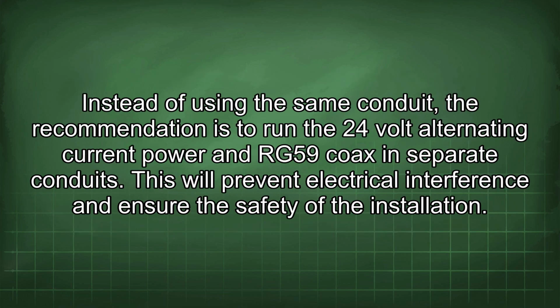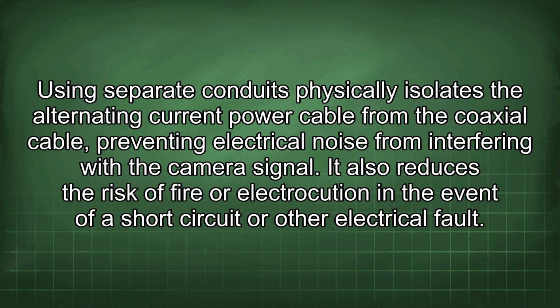Instead of using the same conduit, the recommendation is to run the 24-volt alternating current power and RG59 coax in separate conduits. This will prevent electrical interference and ensure the safety of the installation. Using separate conduits physically isolates the alternating current power cable from the coaxial cable, preventing electrical noise from interfering with the camera signal.